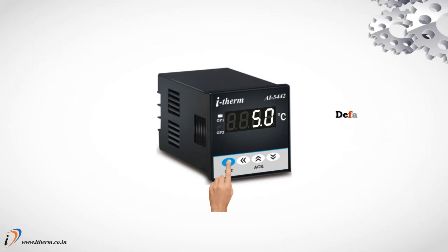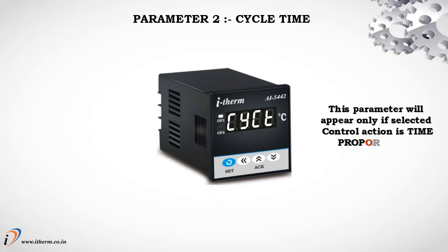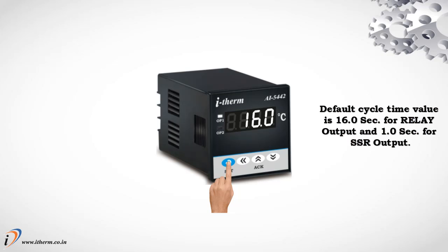Default value for proportional band is 5.0. Parameter 2. Cycle time. This parameter will appear only if selected control action is time proportional. Default cycle time value is 16.0 seconds for relay output and 1.0 second for SSR output.